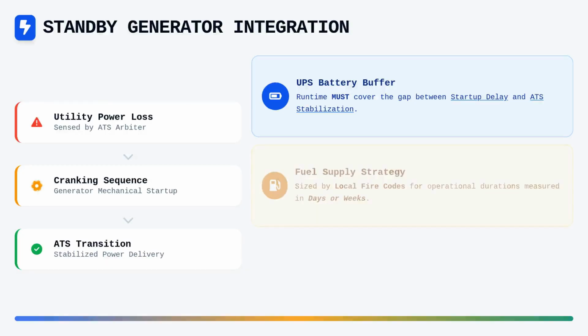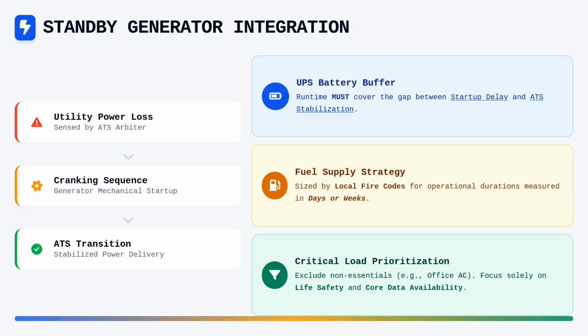Fuel storage sizing is typically dictated by the local jurisdiction's fire codes and the required operational duration, often measured in days or weeks rather than just hours. Furthermore, you should prioritize critical load panels so that the generator is not inadvertently tasked with supplying non-essential infrastructure like climate control for general office space during an emergency. The goal is to sustain only the systems that preserve life safety and maintain core data availability when utility power is absent.